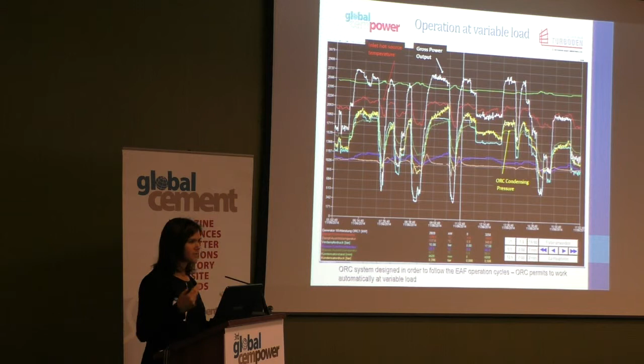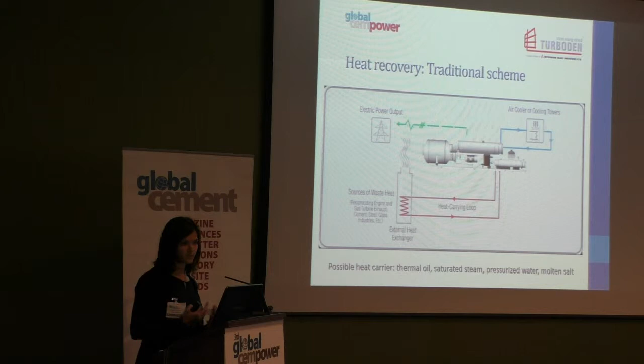In heat recovery applications, the traditional scheme uses a heat carrying loop between the exhaust gas and the ORC. Turboden produces the ORC only, so we work in contact with several heat exchanger producers, and especially in the cement application we know several companies that can handle this part. Normally there's a heat exchanger that heats up a heat carrier. The heat carrier can be thermal oil, which is the most used up to now, saturated steam, pressurized water, or even molten salt—any kind of heat carrier used in the industry.